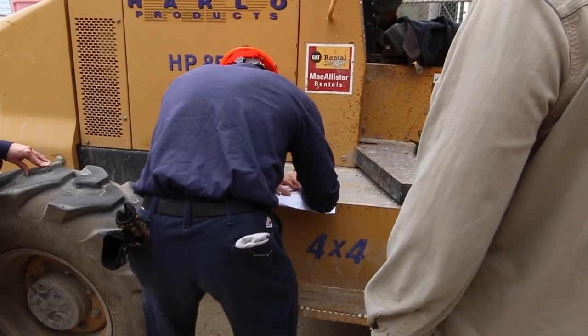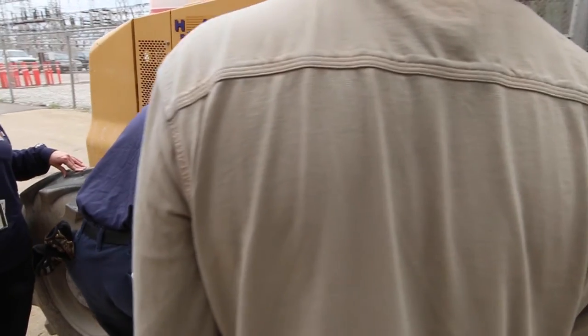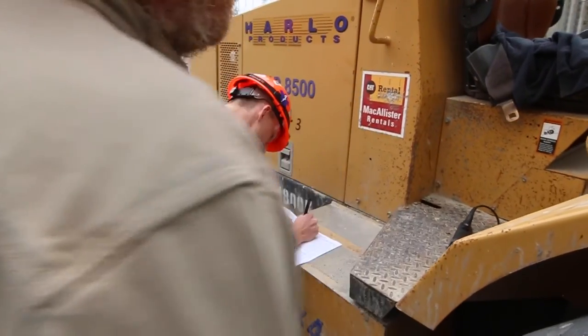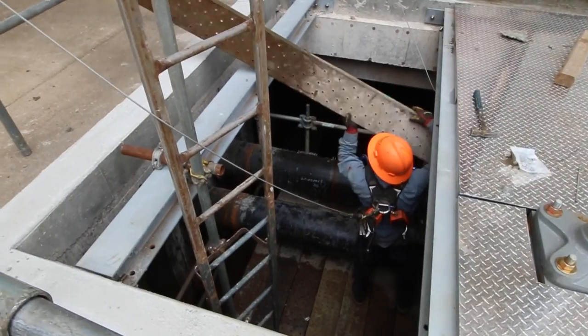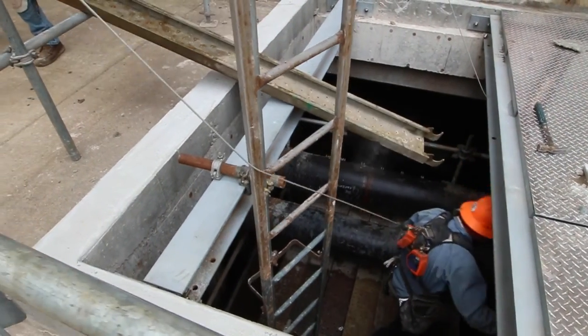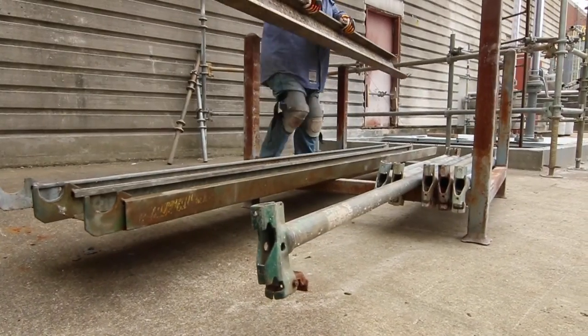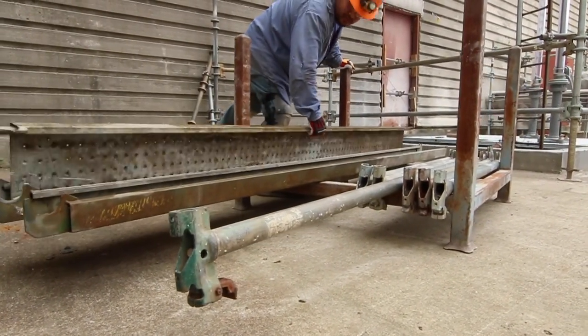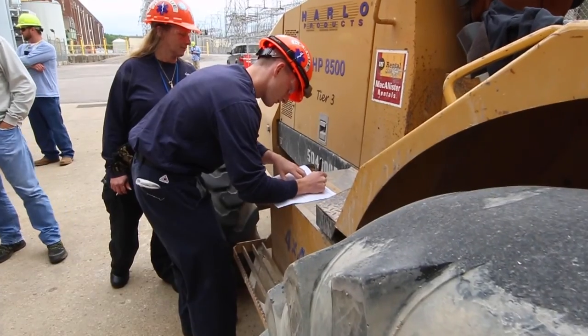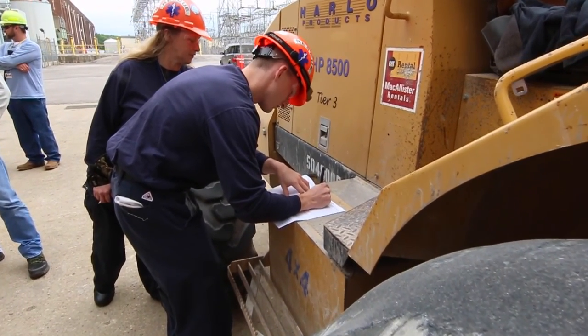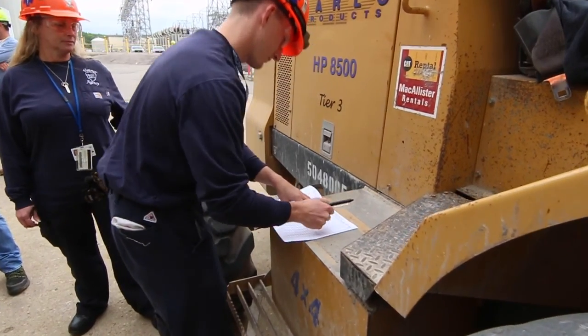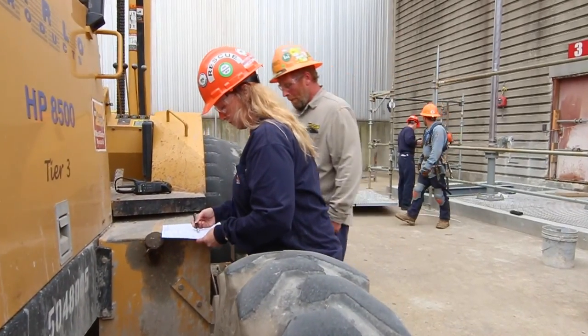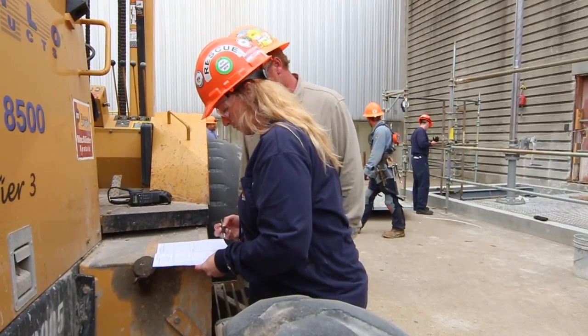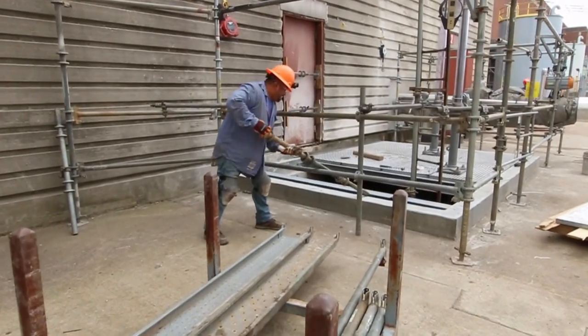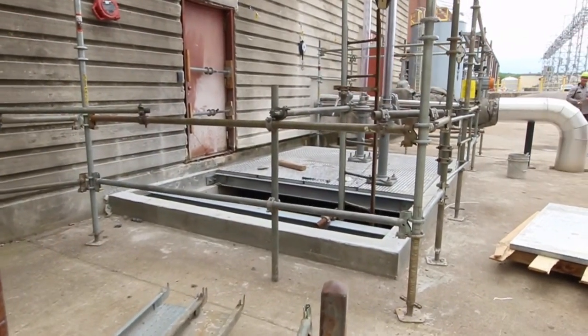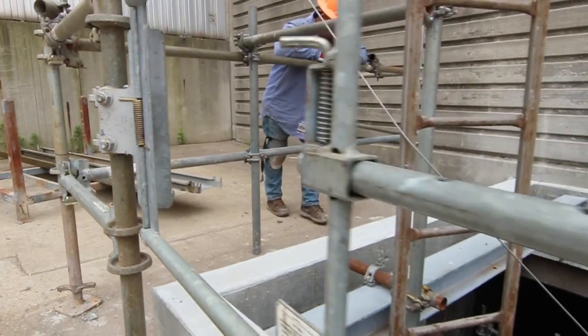Qualified rescue teams are required to be signed on to the entry permit for all high-hazard, permit-required, confined spaces. The contractor is responsible for training and providing the rescue team. During outage periods, IPL may provide the rescue team through contracted services. A communication channel with the assigned rescue team shall be established prior to entering the confined space. The rescue team is required to have a radio and shall document on the permit the name of all entrants and their time of entry into and exit out of the confined space.